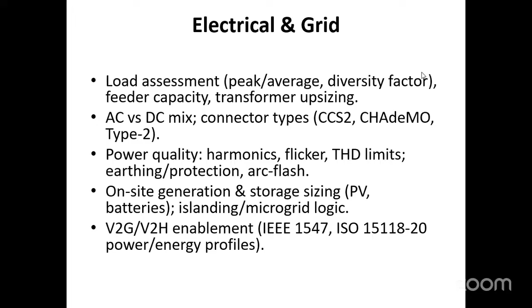Then AC versus DC mix, connector types like CCS2 and so on, power quality, on-site generation, storage sizing, islanding or microgrid logic, and V2G or V2H enablement. These all come under electrical and grid. Careful load assessment is needed to size feeders and transformers, considering peak demand, diversity factors, and harmonics. Choices between AC and DC charging, connector standards, and integration of on-site solar batteries and microgrid logic ensure grid stability. Future readiness includes V2G or V2H capabilities following IEEE and ISO standards.